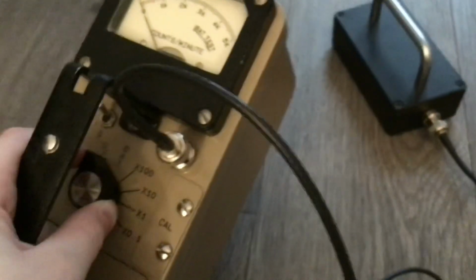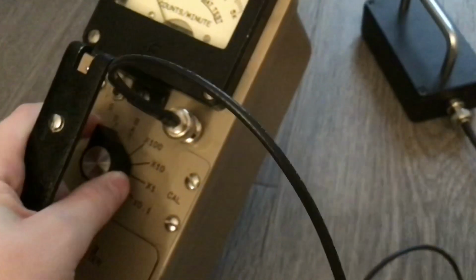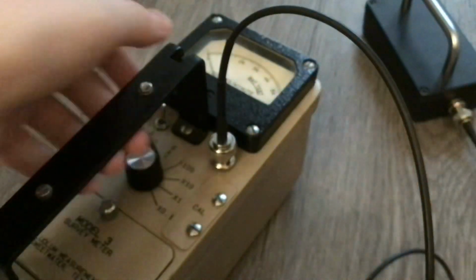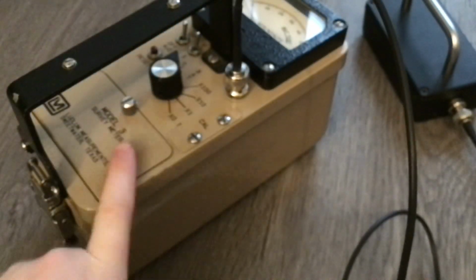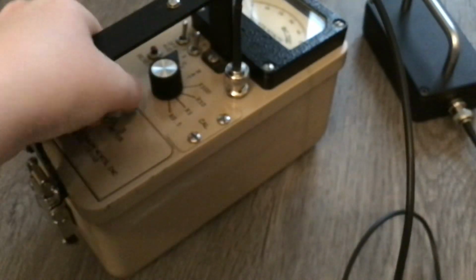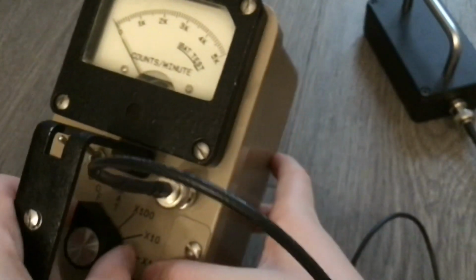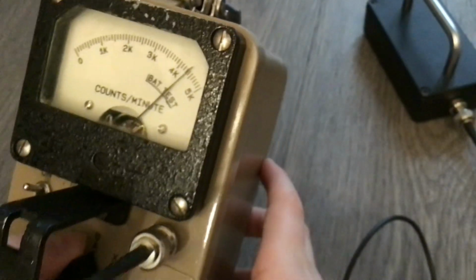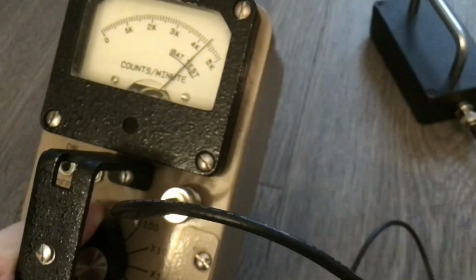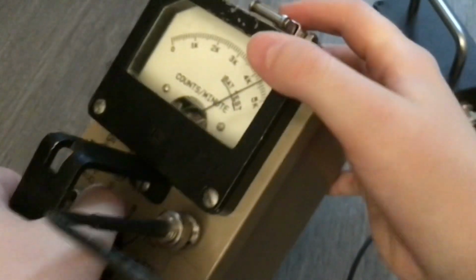You use this little rotary switch right here. The first thing you're going to do is, because this is an analog unit and not a digital unit, it cannot check its own batteries, which, by the way, are replaceable. It runs on 2 D cells right here. Undo the thumb screw that I was talking about earlier. Because it can't check its own battery, you have to manually do it. It's not hard though, all you do is flip this little rotary switch to battery test. It says bat, and then up here should read within the battery test range.